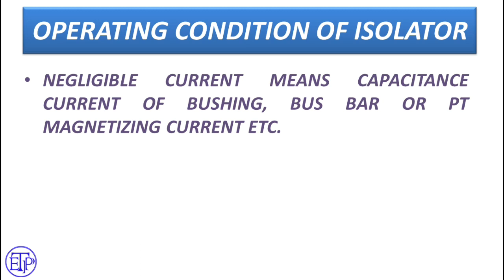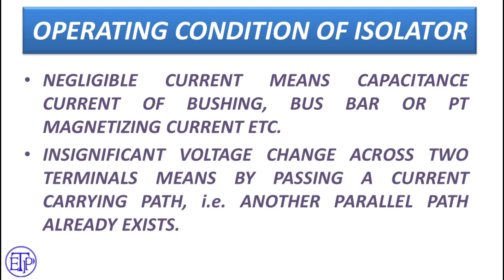What does negligible current mean? Negligible current means capacitance current of bushing or bus bar, or PT magnetizing current, etc. These currents could be directly broken or made by the isolator. And insignificant voltage change across two terminals means you are adding a bypass path to the current — that means another parallel path of current already exists. Under this condition, you can also operate the isolator.